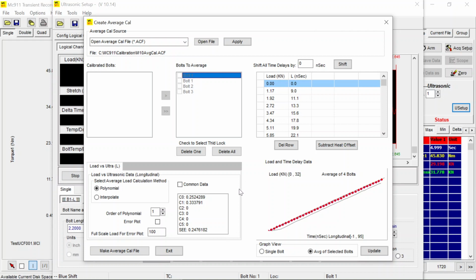And then we calibrate. If you want, you can eliminate any of them. For instance, if you don't want bolt 3, you can delete one, and it goes out of this average calibration group. One more thing I want to point to is common data. Common data means the least amount of data that's common between all these bolts. At this point, if I uncheck this, you see the longitudinal data is -1 to 95 and 0 to 32 kilonewton. If I click on it, the common amount of data between all these three bolts is 0 to 27 kilonewton, and the time delay data is 0 to 82 nanoseconds. So that's the function of this common data.